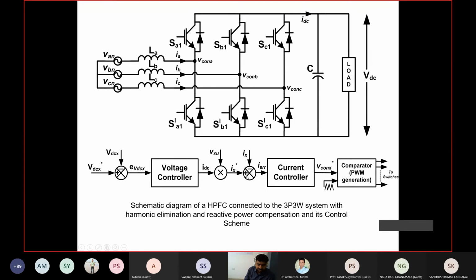That means you will respectively compare the reference AC current minus actual AC current here. IA, IB, IC are nothing but IX commonly. This is the reference current generated by your calibration. Then you subtract, find the AC error current, and go for PI control. This generates the reference signals, reference voltage VCON A, VCON B, to achieve both targets: maintaining the DC voltage constant and maintaining power factor unity with the grid. The VCON X are generated.